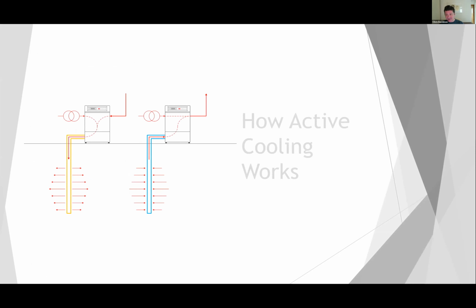This is how active cooling works. On the blue ground loop there's a heating ground loop, where we put cold water into the ground. That water sucks heat out of the ground, the heat is then put into the heat pump, and the electrical energy consumed by the heat pump also ends up as heat, which we then put into the building. Technically this is called heat of extraction - the heat we're extracting from the ground - and heat of rejection - the heat we're rejecting into the building.